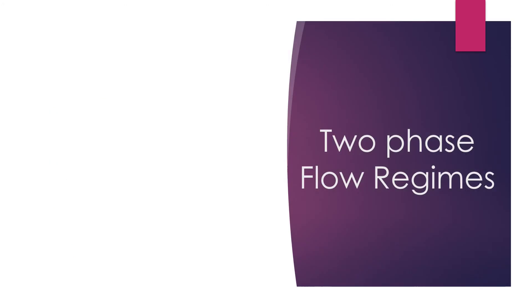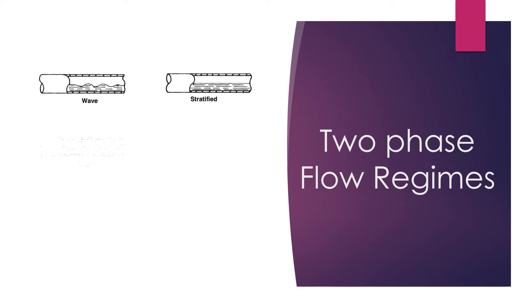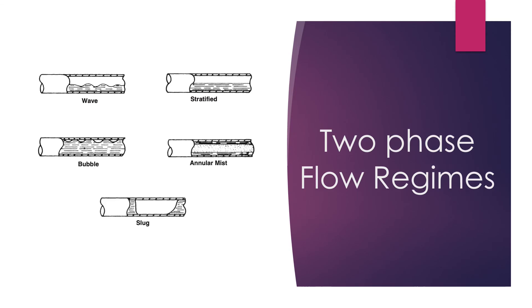Two-phase flow is the most critical type of fluid flow because its calculation is much more complex. It is very sensitive to changes in fluid conditions and pipe orientation, which can cause changes in flow regimes. There are various types of flow regimes for two-phase flow: wave flow, stratified flow, bubble flow, annular mist flow, and slug flow, which is the most dangerous one. Slug flow is undesirable as it can cause vibration and severe damage to the pipe.